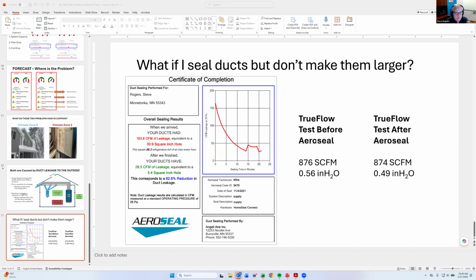But even so, what didn't happen is my static pressure didn't go way up and my airflow didn't go way down. My leakage was pretty modest. 163 CFM is not horrible. It certainly wouldn't pass code, but it's not awful. So yes, it's possible when you do duct sealing for the static pressure to go up, particularly if it's extremely leaky. If you have large gaps that are open, it could go up, but I think probably less than most people think. And if you think about it, a 30.9-inch square hole is smaller than a 10 by 4-inch supply register, and a house is going to have like 20 supply registers of that size. So if the holes you're sealing are equivalent to about 1/20th of your supply registers, it's not going to have a large effect on the static pressure.